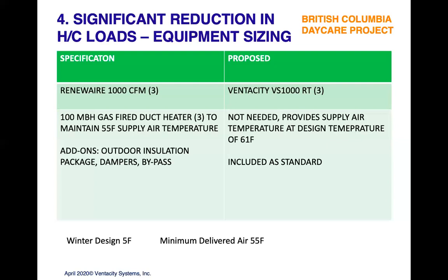And they were looking at some add-ons for the equipment as well. But the big thing is we were able to deliver 61 degrees at the 5-degree design temperature using very high efficiency, passive house efficiency ventilation systems. So we did not need a gas line, gas heaters, gas lines inside the building and controls to run post heating. We were able to deliver to their design temperature without doing that. So it can have a huge impact even on first cost.